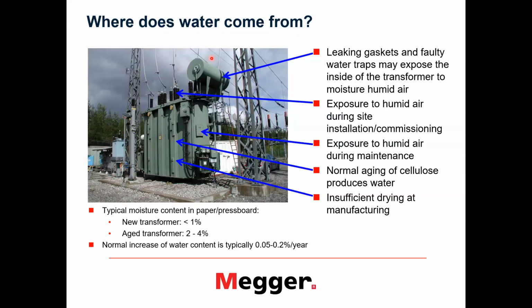And of course, if the transformer is insufficiently dried at manufacturing, that will result in higher moisture content from the very beginning. So here I have written 1% and less than 1% for new transformers. But normally transformer manufacturers aim for lower than that, like 0.5.